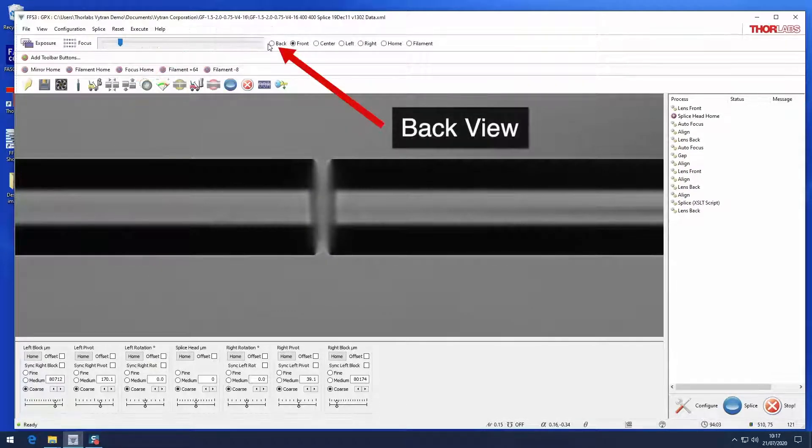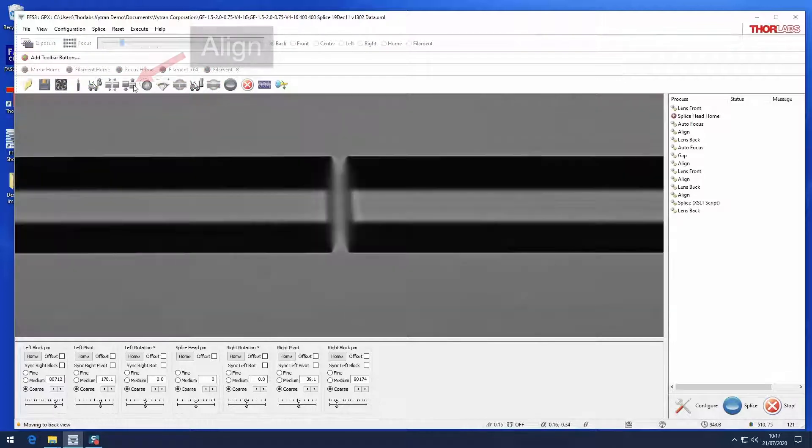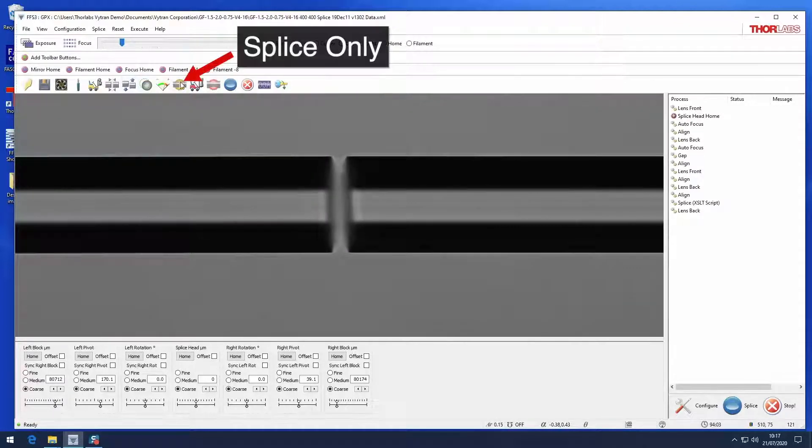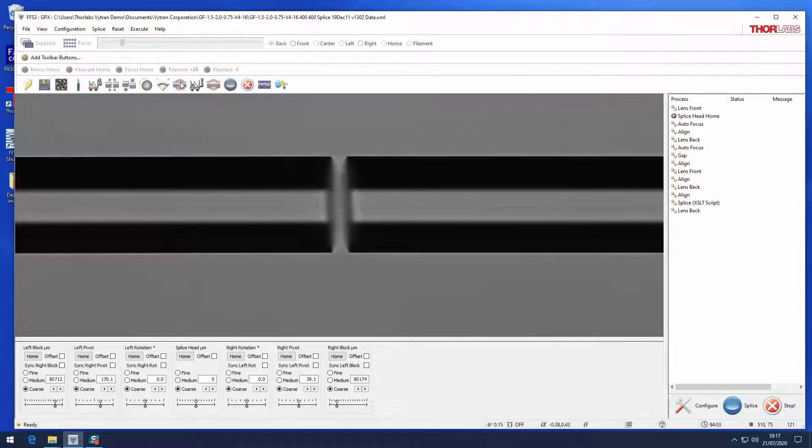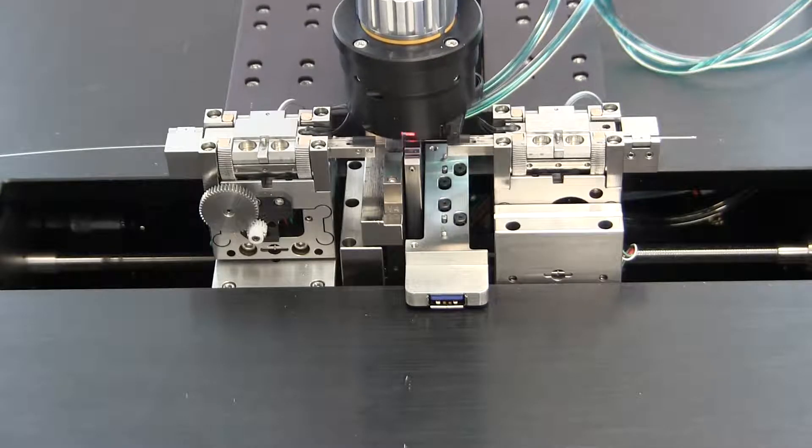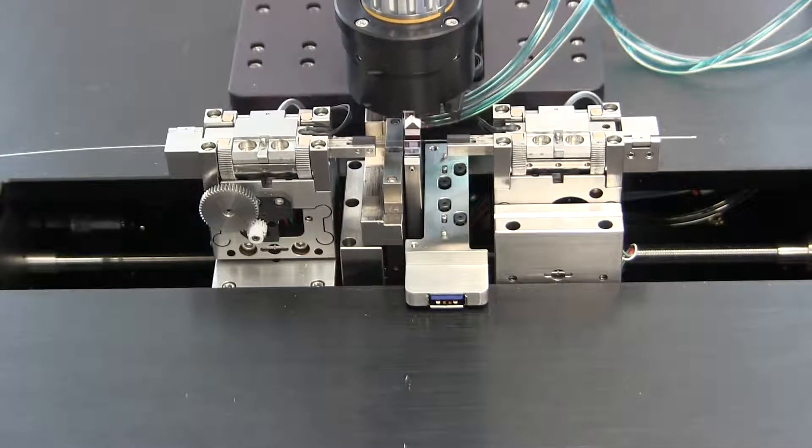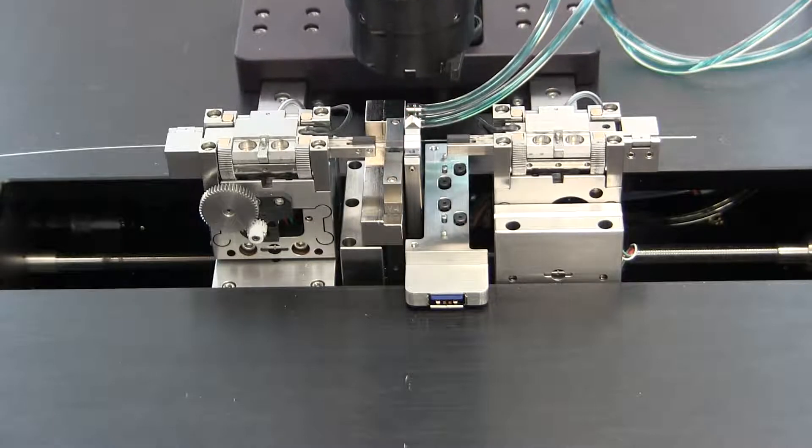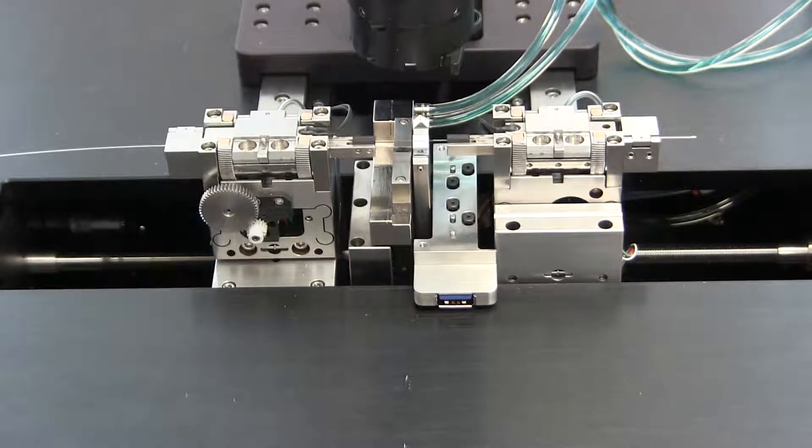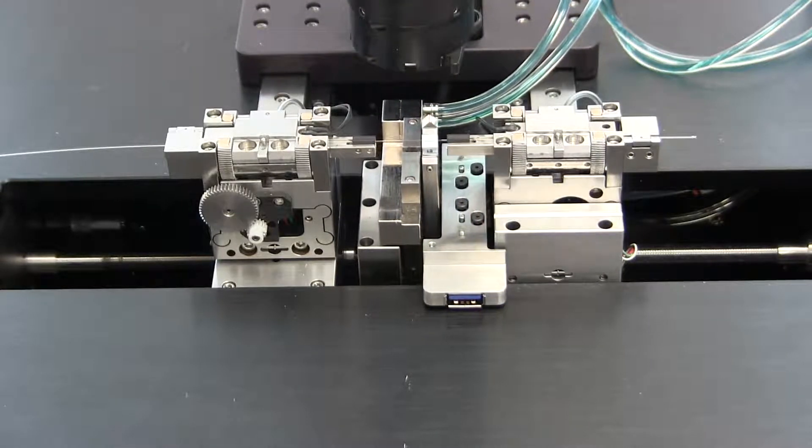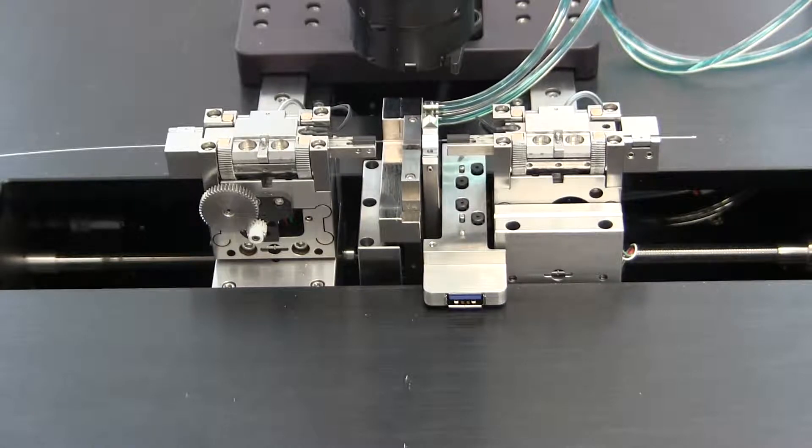It is normal for the screen to go dark while switching views. Click the splice only button to execute the splice process. The camera tower will move to the home position. The splice head will move to the right and the argon rate will increase from the background flow rate to the splice flow rate.